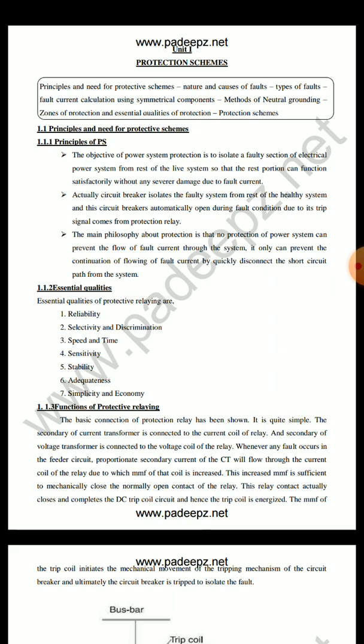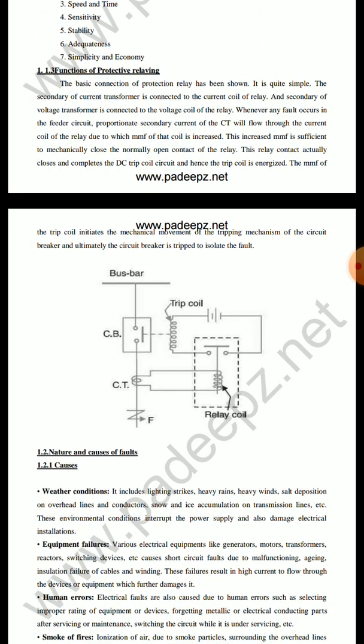In that concept, in every stage from power generation to distribution, we need to protect every set of systems: the bus bar and transmission line, and the transformers, maybe a current transformer or voltage transformer. We need to protect everything. Basically, this is a very simple sample setup. Initially the supply is transmitted through the bus bar.